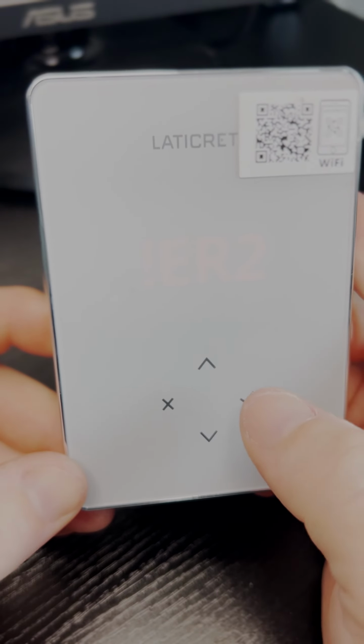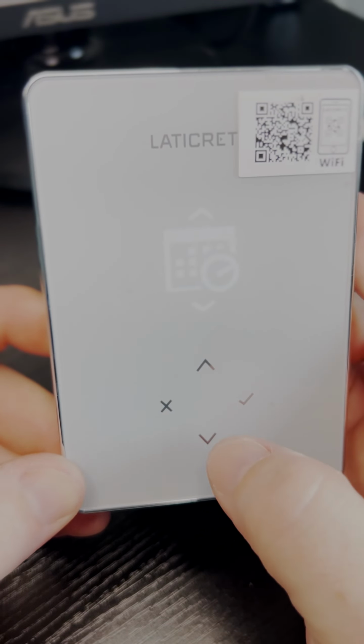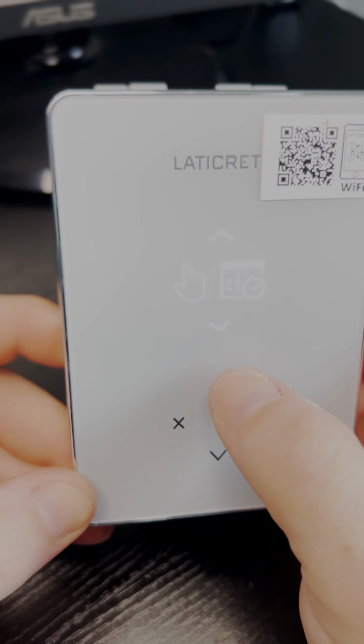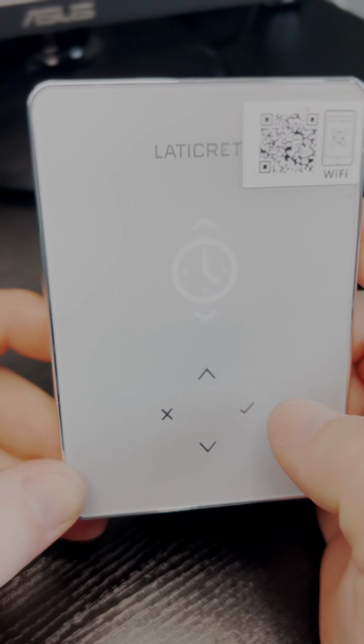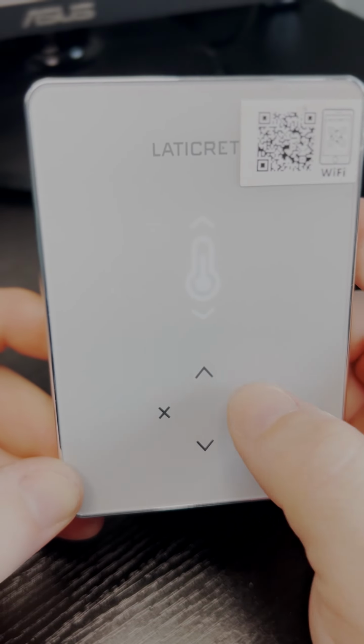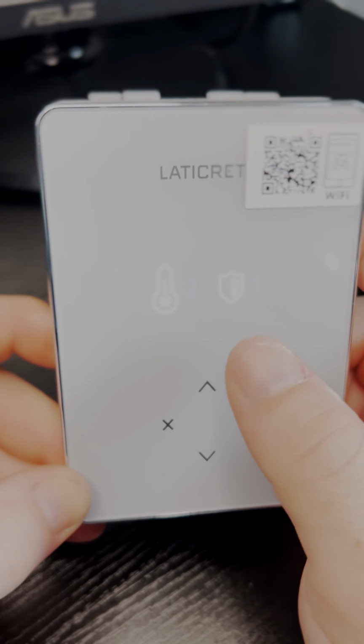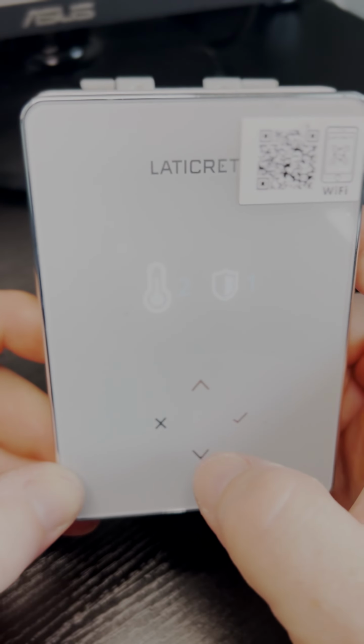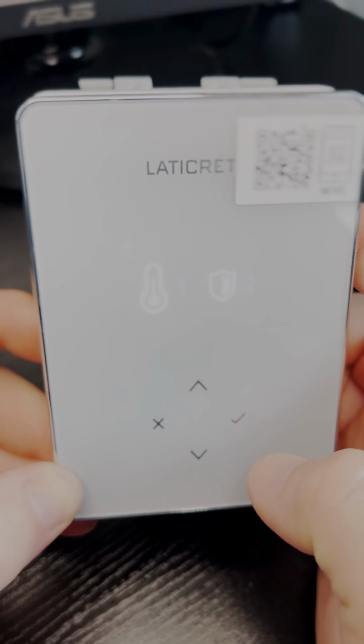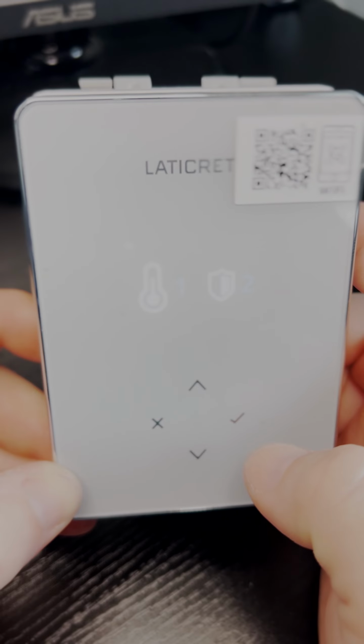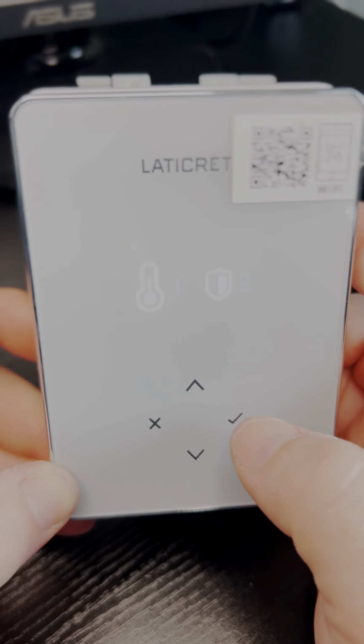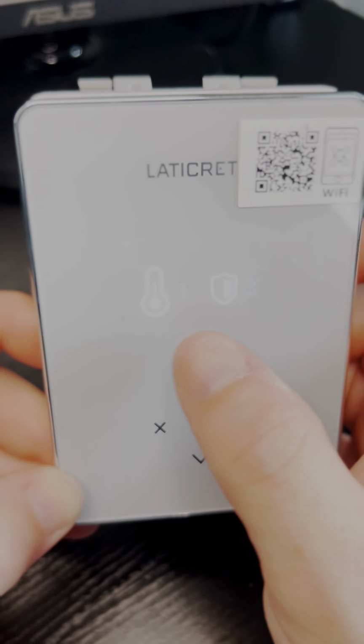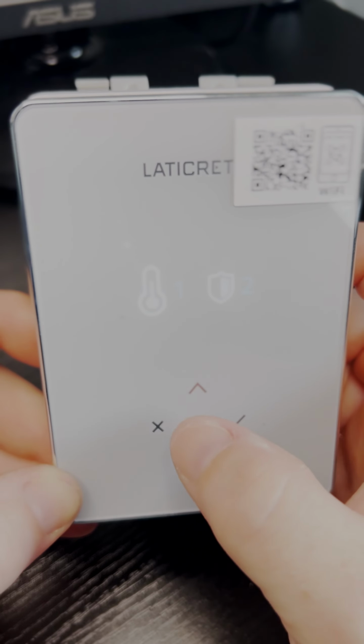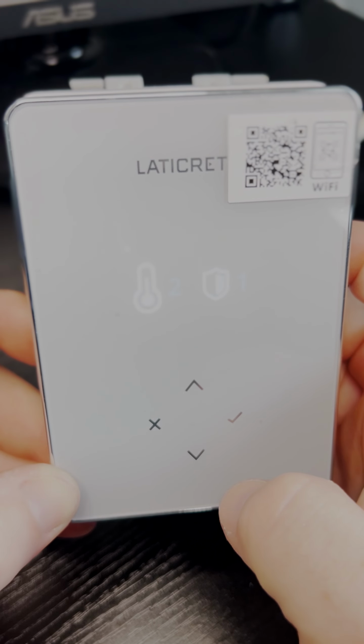So to fix that, I'm going back into my settings here. You can see I can navigate through all kinds of options. I'm going to make sure my probes are swapped around properly. Now I've got my thermometer in 1 on the left, my shield and my 2 on the right — in other words, I'm reading control and limit this way rather than when they're swapped.